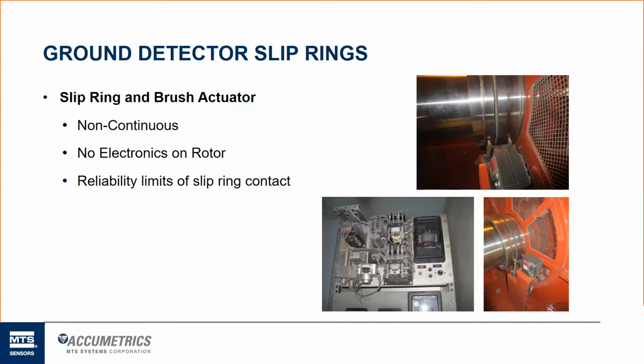So most classical ground detectors are connected to the negative side of the field and rotor ground. They have these brushes that touch down, graphite brushes, I believe they are, that are powered by a solenoid. They touch down on the shaft as it's spinning, usually once per day. They inject a DC voltage that biases that negative side of the field slightly higher than rotor ground, and then it looks for current flow between the negative side of the field and rotor ground. If there is current flow, there is some circuitry that will detect if the resistance threshold is below a certain point. Usually that's set at 10K ohms. Anything below 10K ohms will trigger an alarm and let the user know you've got a ground fault.